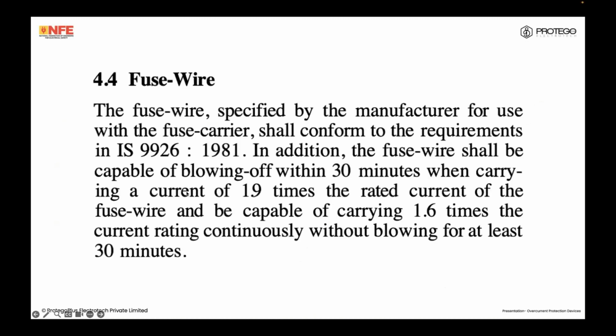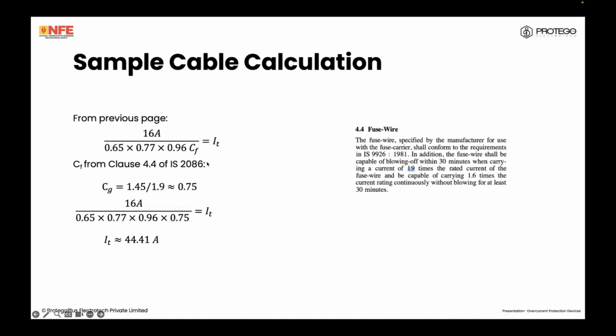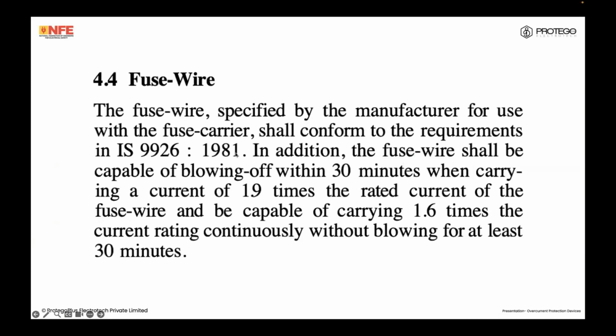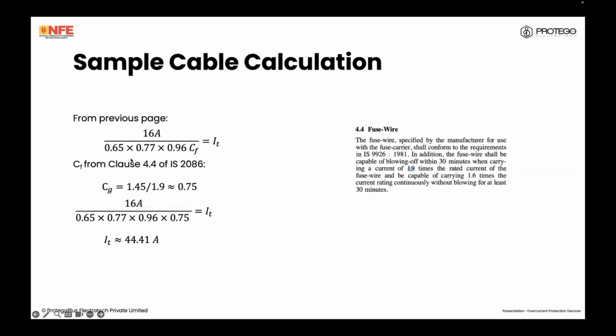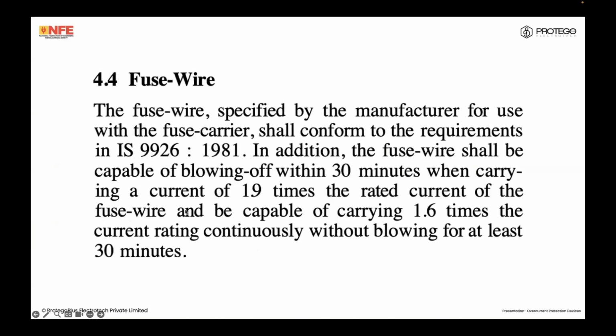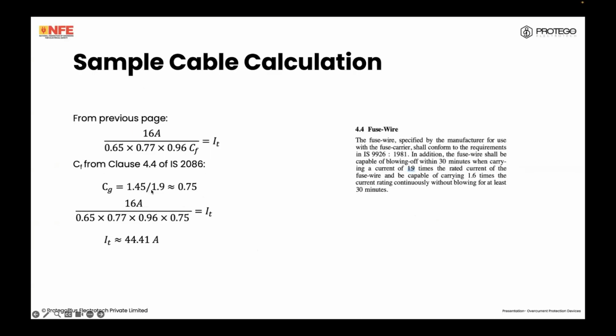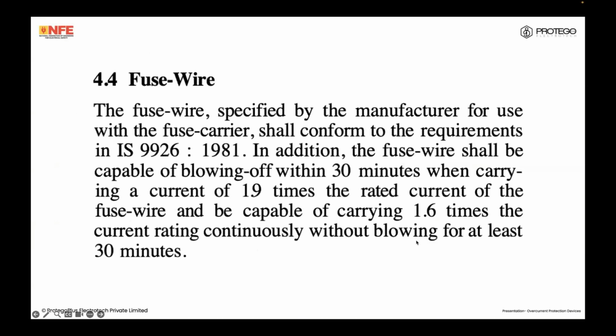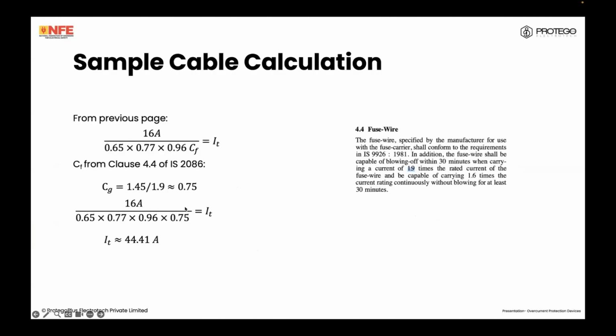0.96, there we go. Fusing factor, this is a 2086 fuse. It has a 1.9 IN fusing factor with a conventional tripping time of 30 minutes. Therefore, I'm terribly sorry, 1.6 and 30 minutes. From the previous page, we'll put in 0.75 because 1.45 divided by 1.9 is 0.75. Hold on, I'm sorry. Yes, sorry, it is 1.9, not 1.6. So that's 0.75. Therefore, we know that we need the cable to carry a tabulated current carrying capacity of 44.41 amps.